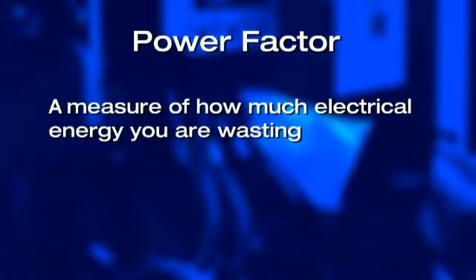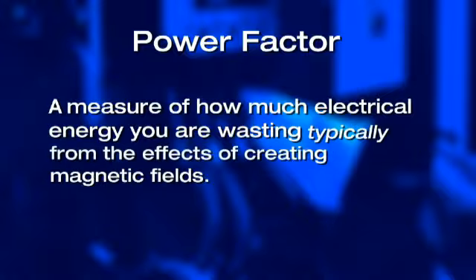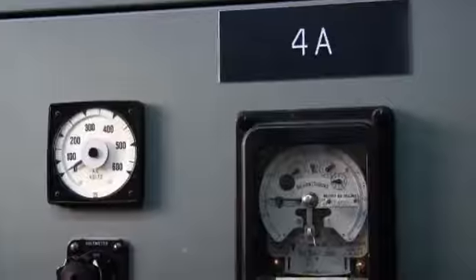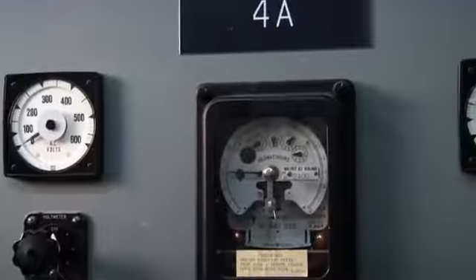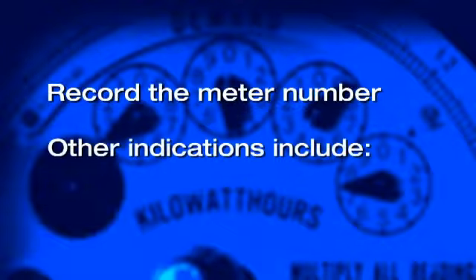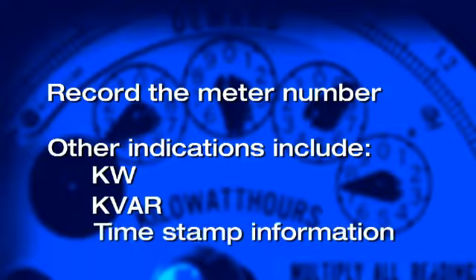Power factor is a measure of how much electrical energy you are wasting, typically from the effects of creating magnetic fields, such as in motors and transformers. Most utilities prefer that you keep your power factor values as high as, say, 0.92 or 0.95 or even better. Start your power factor survey at the utility meter. If you're being charged for power factor, their meter should have a power factor readout function. When observing the meter, be sure to record the meter number. Some other indications you can expect to see include kW, kVARs, and timestamp information used for time of day billing.